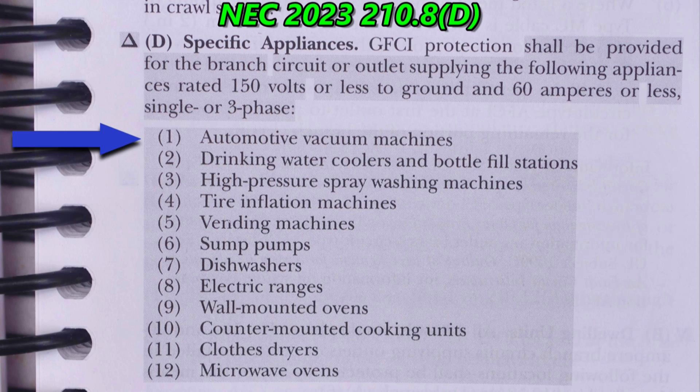An important note on this subject is that the fear of a tripping GFCI device is a reason that states such as Oregon continue to allow non-GFCI protection for refrigeration equipment. Oregon allows this where a single receptacle is installed and labeled 'not GFCI protected.' The kitchen GFCI protection in the NEC may be amended per jurisdiction, so I advise checking before doing work of this kind.